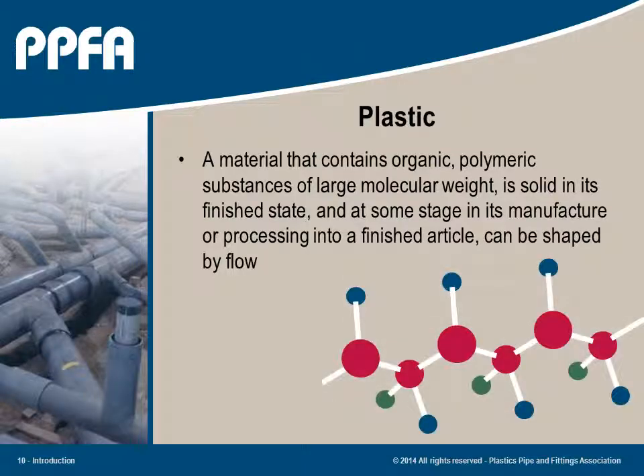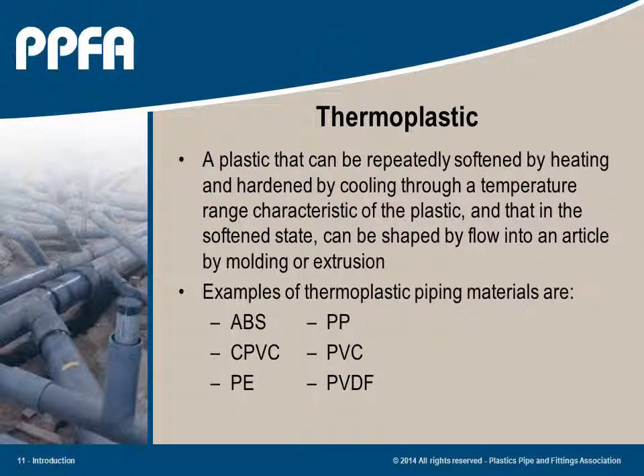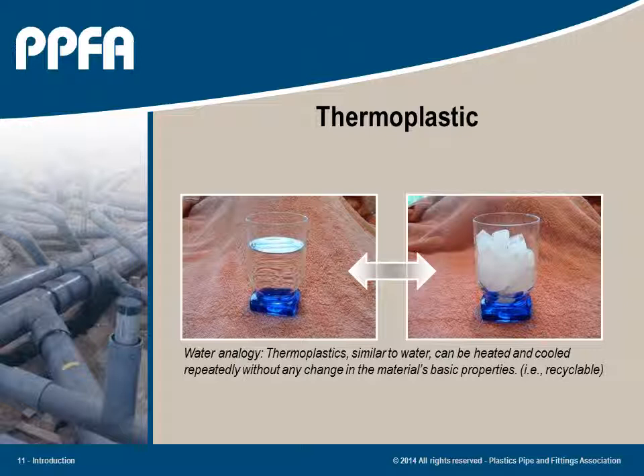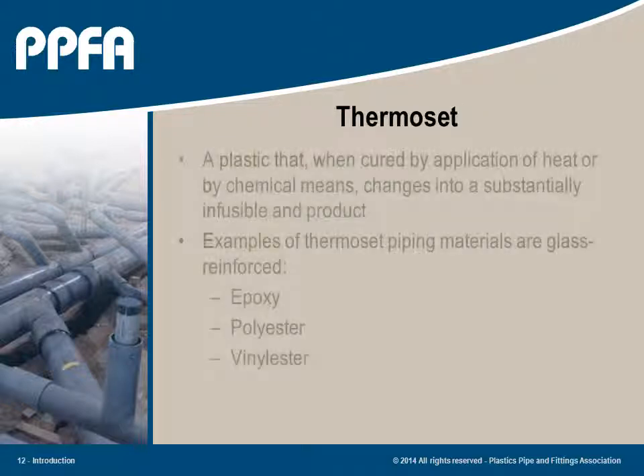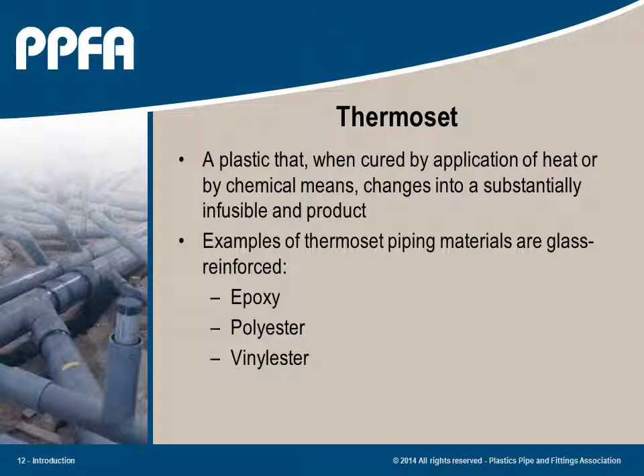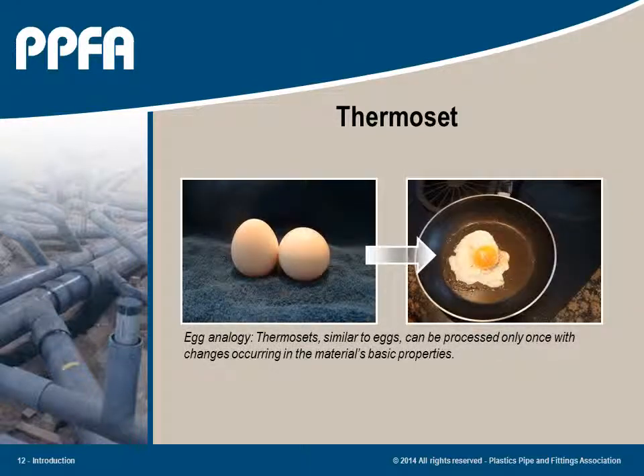The word plastic is derived from the Latin word plasticus or the Greek word plastikos. Both mean the same, to mold or shape. There are 2 major plastic categories, thermoplastic and thermosets. Thermoplastic piping includes, but is not limited to, vinyls, PVC and CPVC, polyolefins, polybutylene, polyethylene, and polypropylene, fluoropolymers, polyvinylidene fluoride, and ABS. Thermoset piping includes, but is not limited to, phenolics, reinforced epoxies, polyesters, vinyl esters, and reinforced thermoplastics.